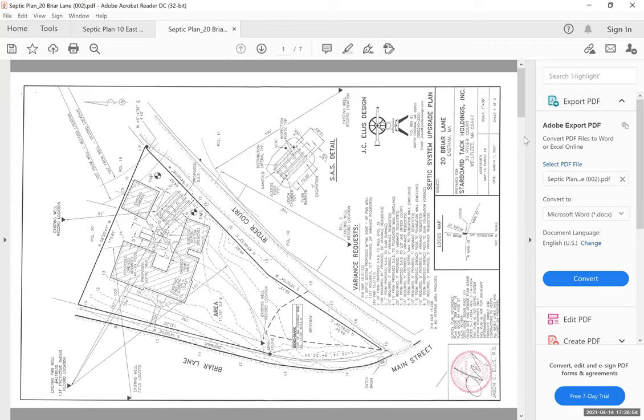Just to get better distribution. Will they be protected? I was just worried about the laterals in the parking area that aren't covered by the concrete structure. Yeah, so some of the laterals will actually go through the chambers. And then the other laterals would be outside, covered up. You'd have the orifice shields on top of the orifices there. Right. And those are usually all schedule 40.